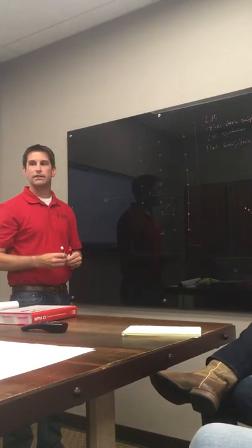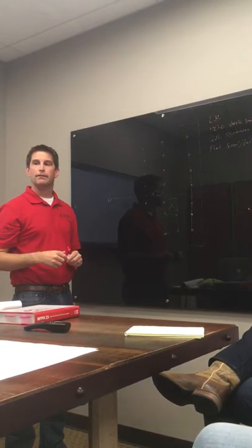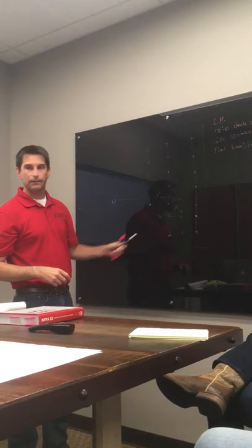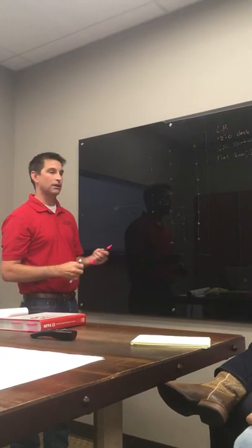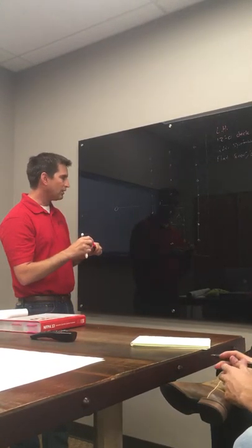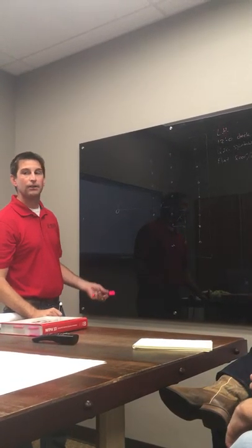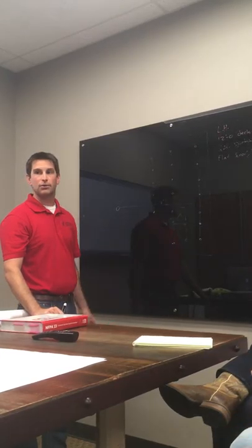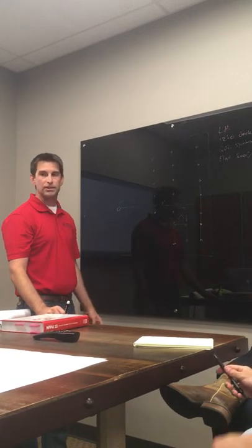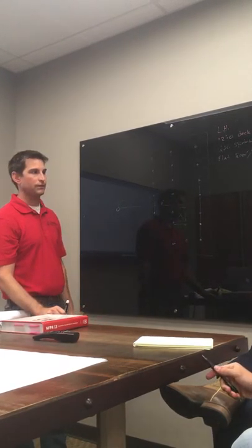Because there's more attached to that branch line that falls into that design area. Okay. That's where people get messed up real quick. And that's what's so hard. It's really easy when you're designing to be like, oh yeah, it's simple, I got a line here, I'll pull off there and go over there. Then you make it really hard for yourself to do your calcs and proof without doing a whole bunch of extra remote areas that you really don't want to be doing.